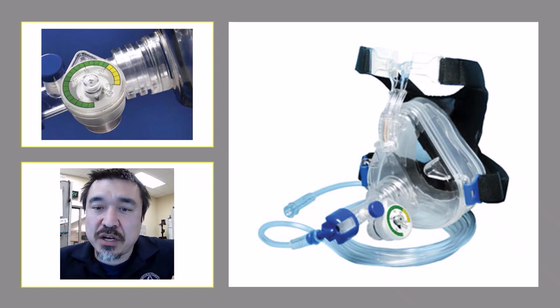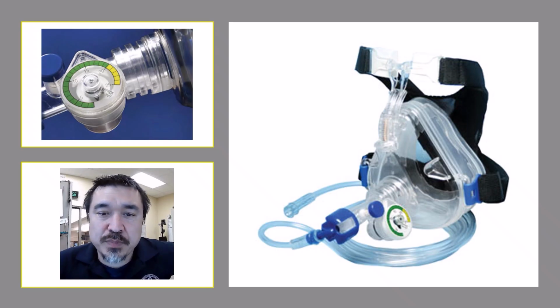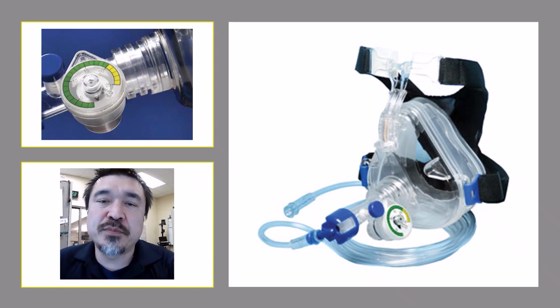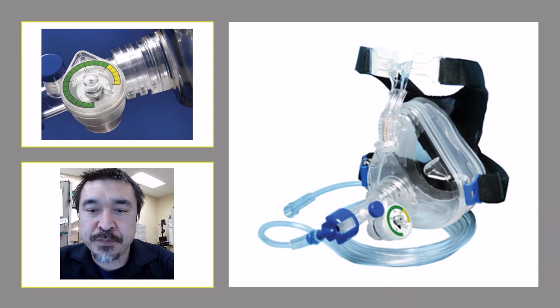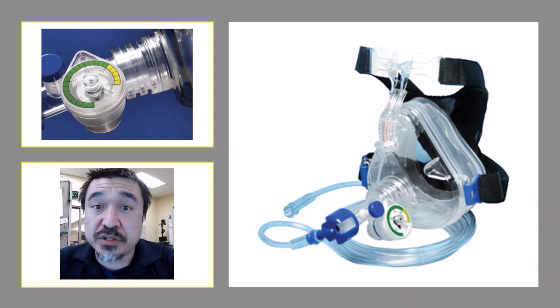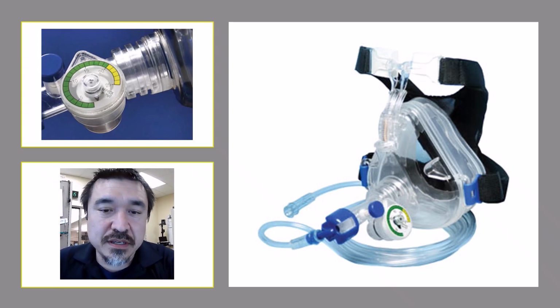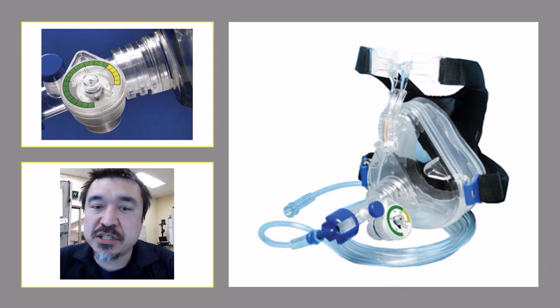PEEP is determined by the flow from your low pressure O2 regulator, and you can verify it using a built-in manometer. This also allows you to verify that you have a good seal. It uses a low pressure from any O2 regulator rather than relying on the high pressure ports and modifications. It provides peak flows well over 100 for those patients that are air hungry and is completely disposable. The best part is it's simple.